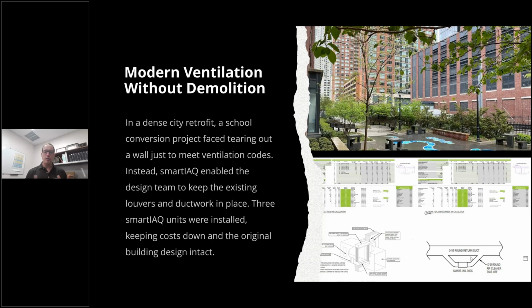Our rep walked in and said, look, we can keep all that and just clean it instead. So long as you have enough air for pressurization, exfiltration, and whatever other needs you need, we can manage the rest of that. In fact, in this instance, we were able to put one smartIAQ unit on each of the water source heat pumps, and there were two, and then we put one in their gym. So three units solved this entire problem and saved them a lot of that construction cost, both on the demolition side and the new side.